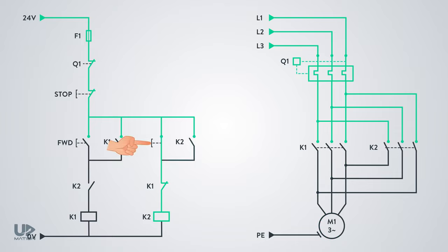The same thing will happen to the reverse contactor. This time, as the order of the two phases has been changed, when the K2 contactor gets energized, the rotation of the motor will be reversed.